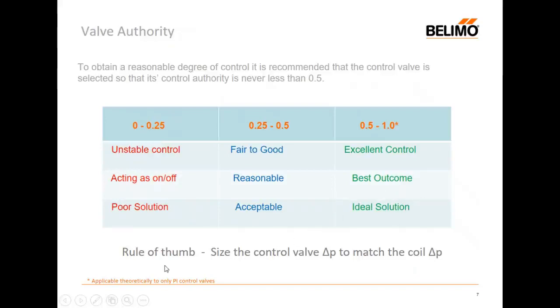And here I've said that as a rule of thumb, when I'm sizing control valves, I should try to match as closely as possible the pressure drop of the coil. Now, in reality, I should calculate the full resistance of the entire circuit, but that's quite a task because I need the linear pressure drops of the pipe, the strainer, the balancing valve, the coil, and the control valve in order to do this calculation that we looked at earlier correctly. So I've made a rule of thumb and said, if you size according to the coil, you're not going to do a bad job.